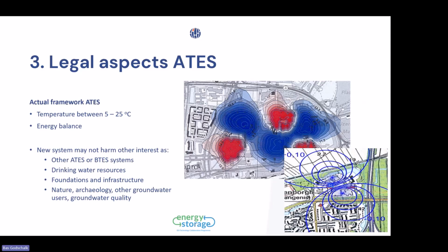For traditional ATES systems, the framework allows you to abstract and inject between 5 and 25 degrees, and you should maintain an energy balance, meaning the amount of energy abstracted and injected should be more or less equal. When applying for a permit, you must consider other groundwater users so you don't harm their interests—something you need to prove by setting up a risk assessment.